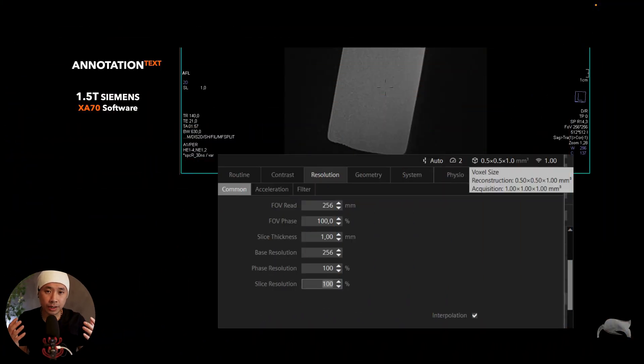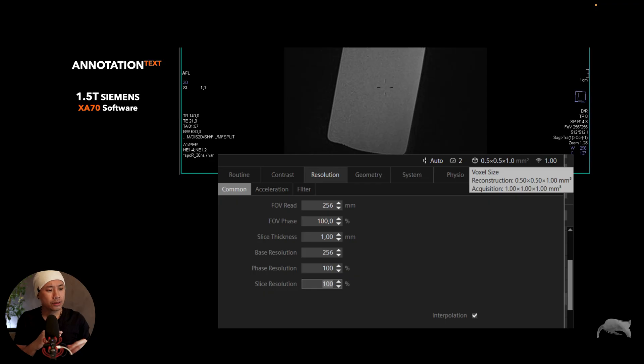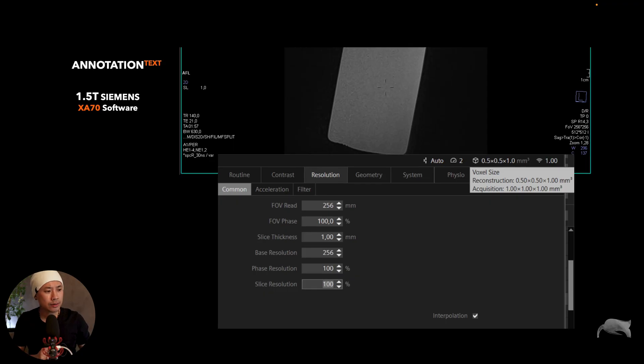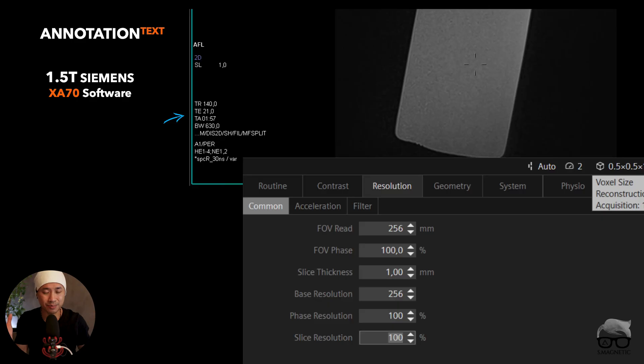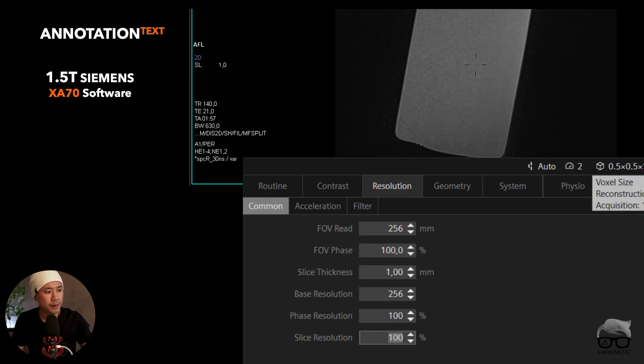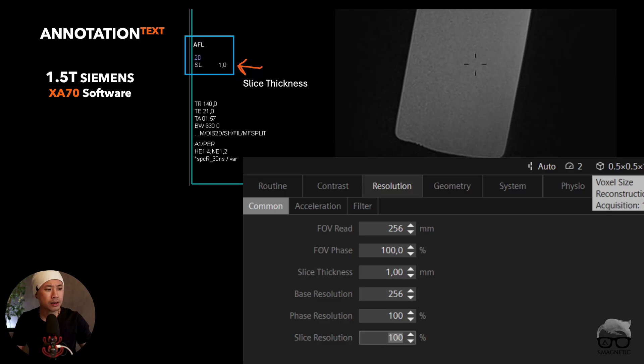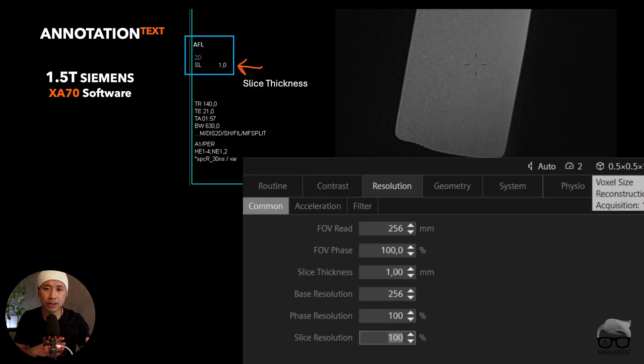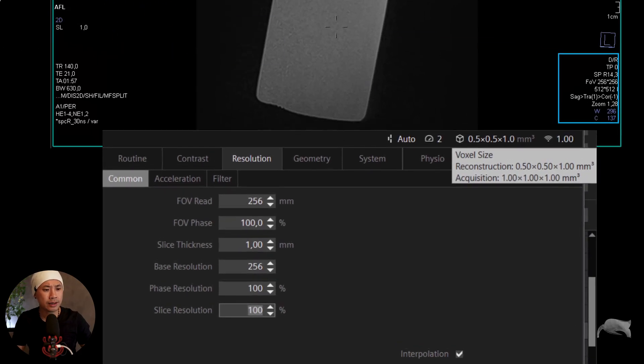Currently we are at the 1.5 Tesla Siemens scanner, it's actually syngo but it's more or less the same with other software as well. So if you look at this 3D sequence right here, do not look at the scan time or the TR/TE parameters because I just pushed maximum and there's no good weighted or good images, it's just a phantom. I just tried to make it fast so I could show the different tags and the different names and highlight which is important. The first one I'll talk about is the slice thickness. It's the same as on the 2D, it says here on this corner and this one is one millimeter. But if you remember from my last video, I was talking about the distance factor - there's no distance factor on 3D because it's a volume.